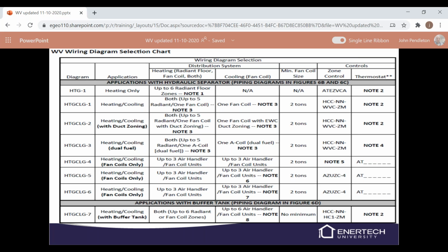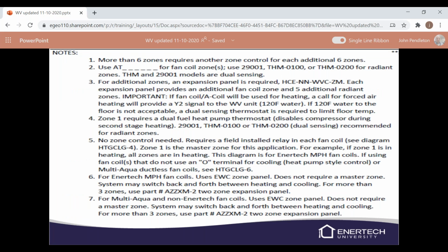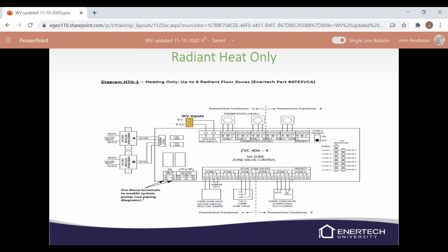With the Hydro Connect, you can usually bring your own thermostats. If you get into some of the HBX controls, you'll have to use the HBX thermostats. Just some notes on zoning. More than 6 zones requires another zone control for an additional 6. Just talking about some different thermostats, not really going to get into that too much. If you're going to use air handlers, we would recommend the MPH fan coils. We can get into some of the multi-aquas, but again, if you're going to get into a smaller air handler, make sure that we're using a buffer tank. If it's 2 tons or larger on the air handler, then we can go ahead and use the hydraulic separator.